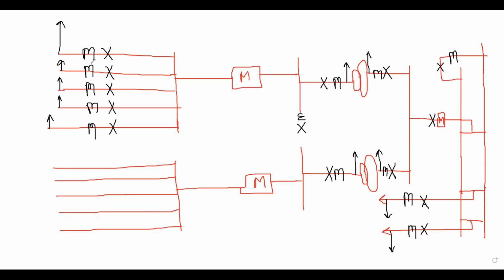And for maintenance, I require the isolators. On either side of the breaker and CTs, we are having the isolators. Because if I want to attend to maintenance, I will open these two isolators and I will do the maintenance, right? So isolators, all the isolators. Now, if I want to take out this meter and do the maintenance, for the maintenance purpose I require isolators here. And to isolate this, I require the isolator.